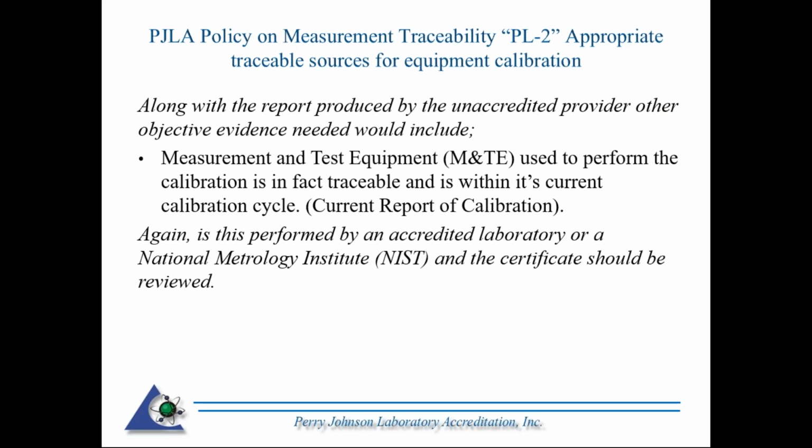So I mentioned objective evidence that would be reviewed. Your organization can plan on, along with the report of the unaccredited provider, the report associated with the equipment that was used for your calibration. Ideally, was it from an accredited source, 17025 recognized, or the NMI?